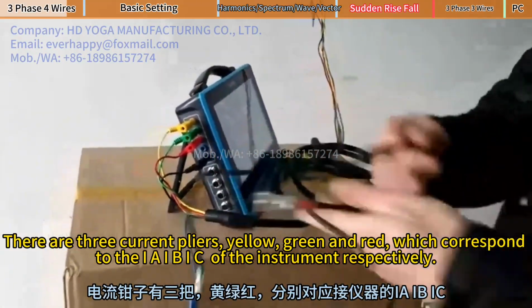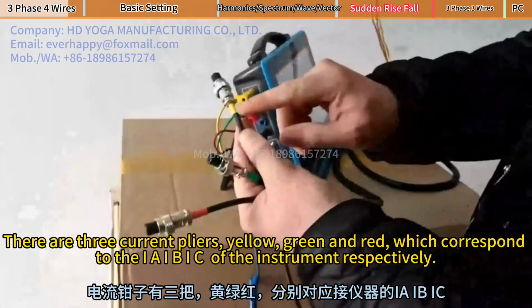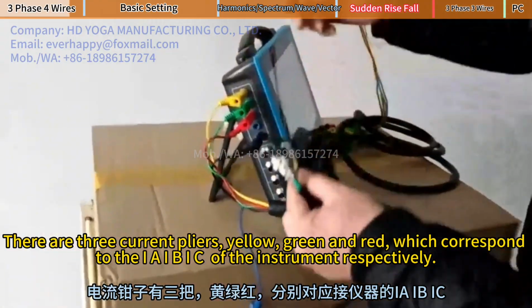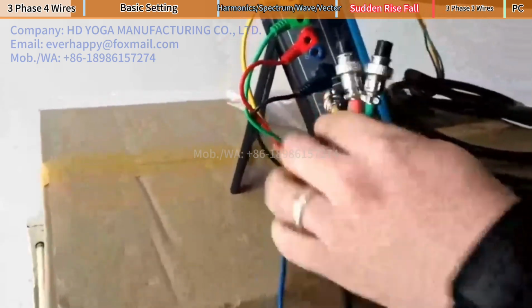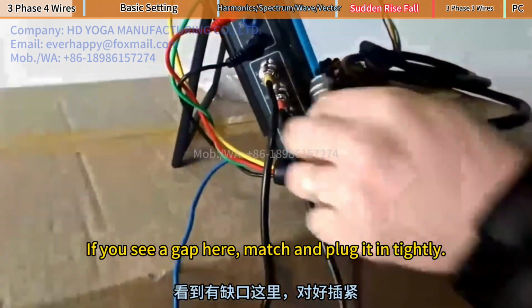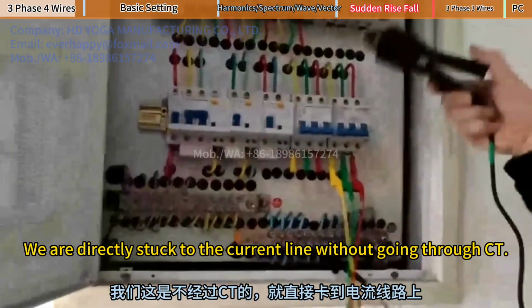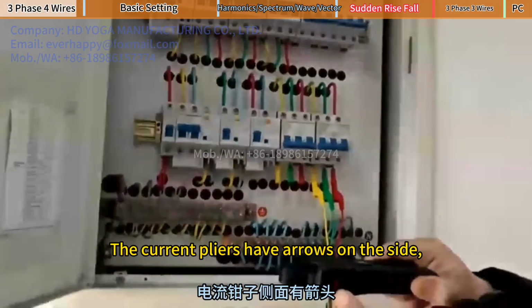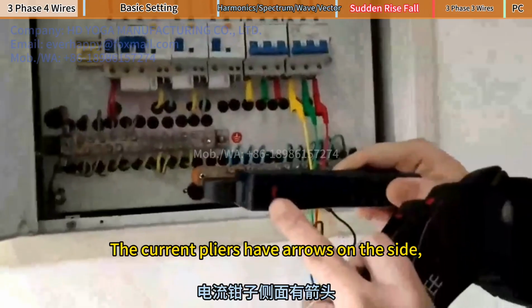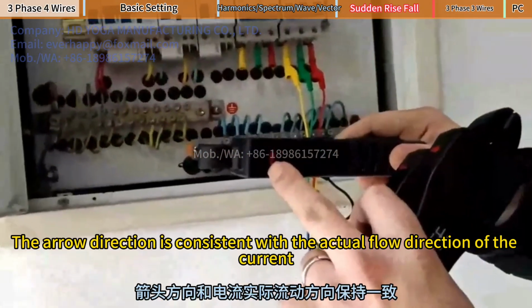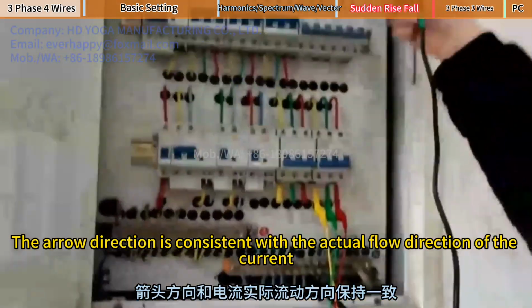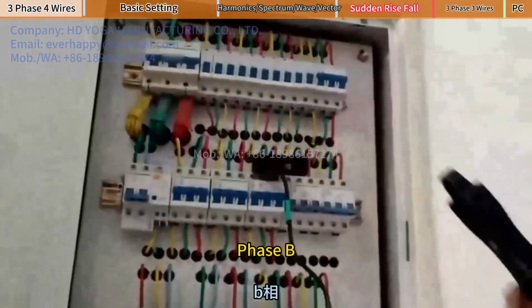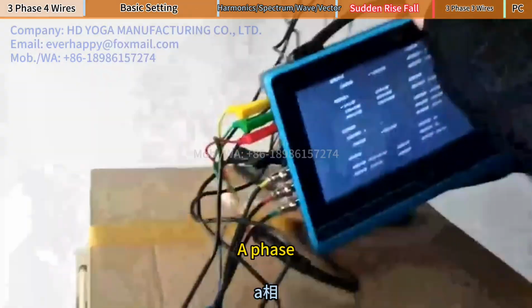There are 3 current clamps, yellow, green and red, which correspond to the IA, IB, IC of the instrument respectively. If you see a gap here, match and plug it in tightly. We clamp directly onto the current line without going through CT. The current clamps have arrows on the side. The arrow direction is consistent with the actual flow direction of the current. Phase A, B phase, C phase.